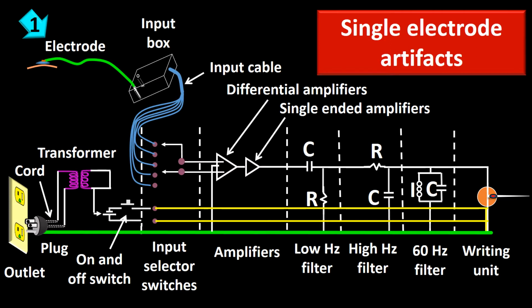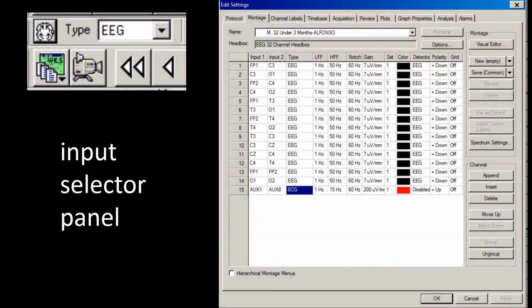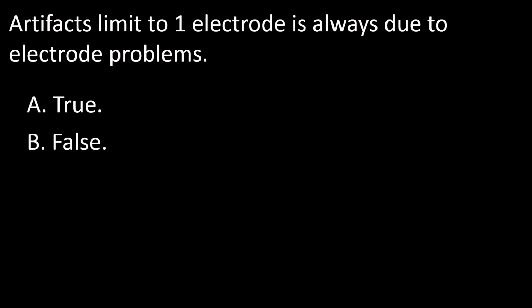They may occur because of a problem at the level of the electrode, the input box, the input cable, or the input selector switch. Input selector switches in current EEG machines, as I pointed out before, are part of the software of the machine. So the answer to this question is false.